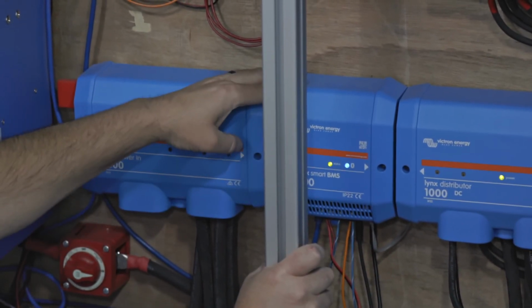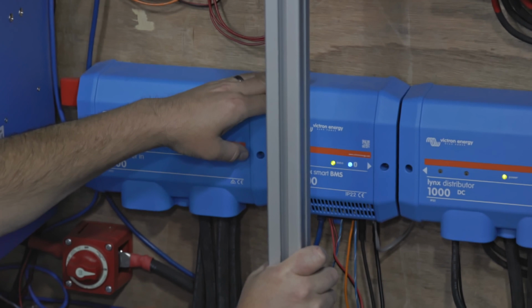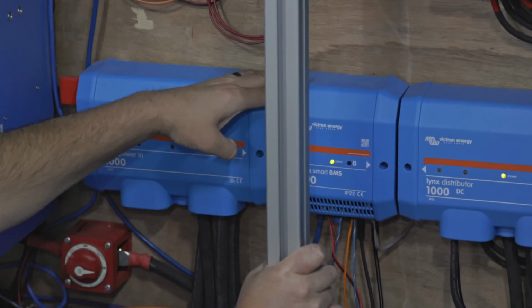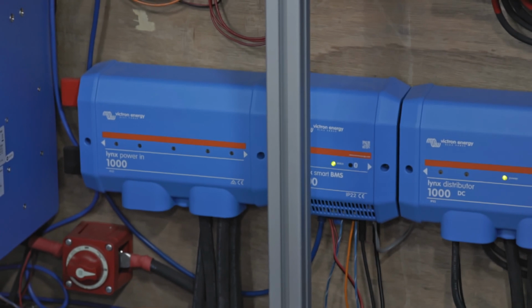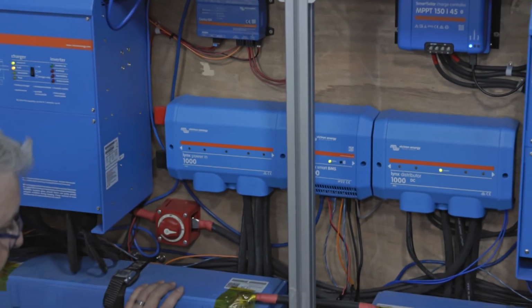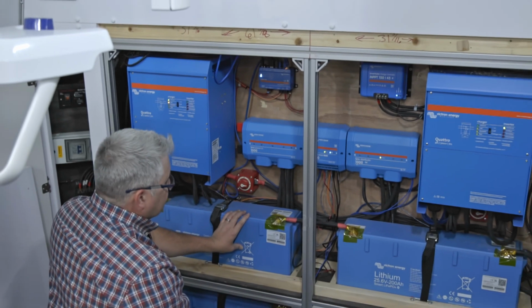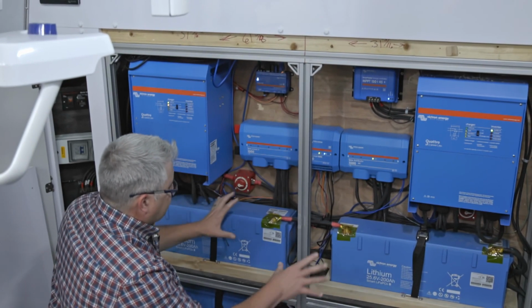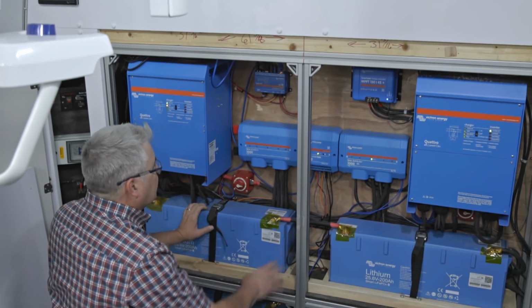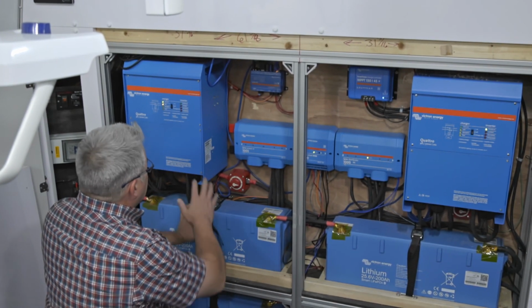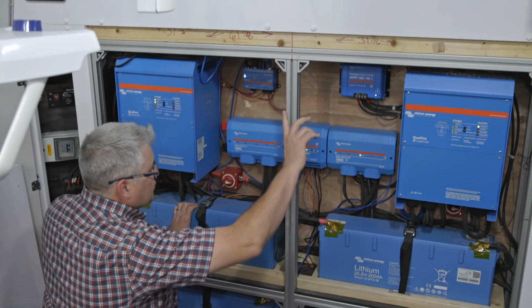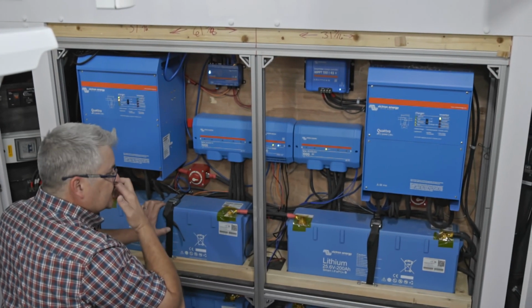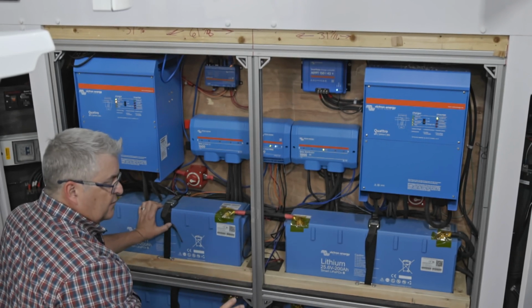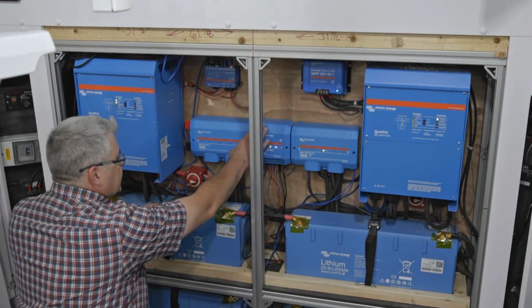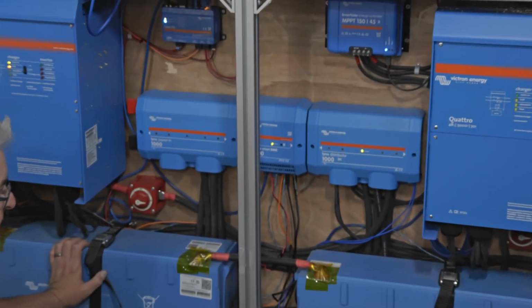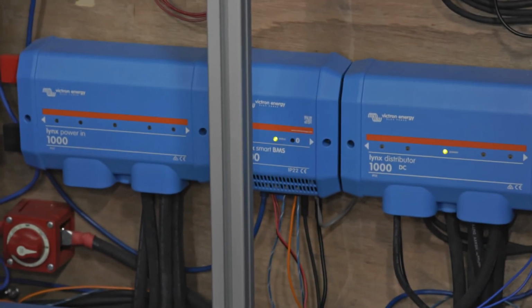And inside of here is a contactor. A contactor is basically just a big heavy duty relay, or a switch, if you like. So if the batteries get near empty, once they get to a certain point, in order to keep the system from completely draining, this contactor is going to open. It means that the inverters won't work anymore. The solar charger is going to be disconnected from the batteries and all that. So there's going to be a little bit of room left in the batteries, even when this says it's 0. I designed it that way on purpose so that they would never hopefully go totally flat.